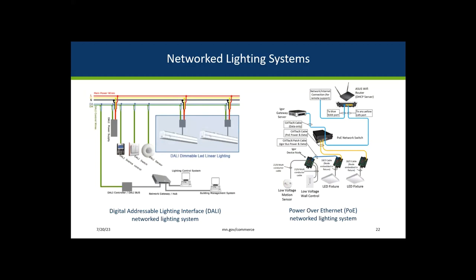This slide shows schematics for two network lighting systems, an AC-powered DALI system and a DC-powered PoE system. These network lighting systems can provide added functionality such as on-off scheduling, occupancy and lighting control, dimming and color tunability, luminaire level control, and integration with the BAS and security life safety systems. Notice the additional equipment that is needed to support this network intelligence, such as sensors, controls, drivers, power supplies, gateways, servers, network switches, and routers. These devices not only add capital costs and operational and maintenance complexity, but also must be powered and therefore incur an energy cost.